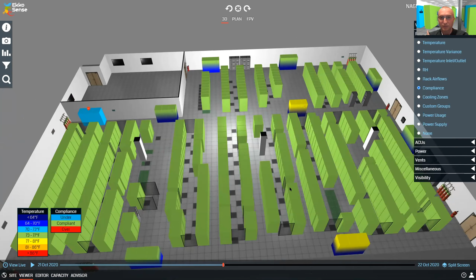Another one used quite a lot by network operations teams is the compliance filter. This is a simple filter to show where racks are outside, either above or below, their temperature thresholds. Those thresholds can be set at a room level or individually at rack level, so you can have custom compliance groups if you have different SLAs for certain parts of the room, certain equipment, or certain customers you're monitoring and reporting for.